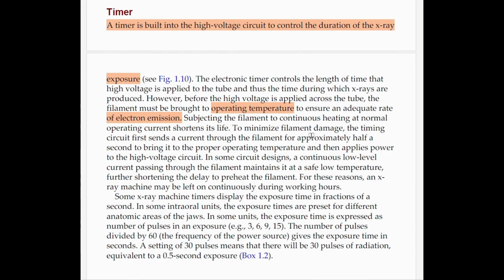To minimize filament damage, the timing circuit first sends a current through the filament for approximately half a second to bring it to the proper operating temperature and then applies power to the high voltage circuit. In some circuit designs, a continuous low-level current passing through the filament maintains it at a safe low temperature, further shortening the delay. to preheat the filament. For these reasons, X-ray machines may be left on continuously during the working hours.